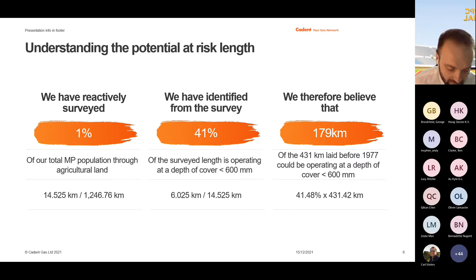In the quantified risk assessment that I developed, I built this in using data available from the Department for Environment, Food and Rural Affairs, DEFRA. Extrapolating this to the total length of pipe laid in agricultural land pre-1977, it indicates there could be 179 kilometres of pipe operating at a depth of cover less than 600 mil, meaning it's a foreseeable risk we need to consider.